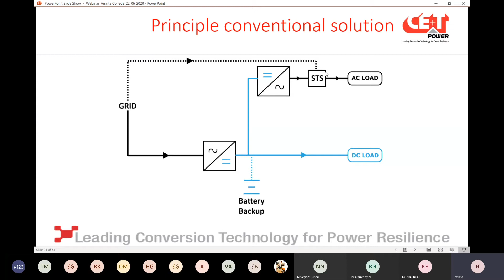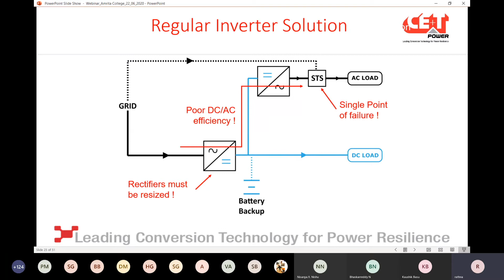There is a single point of failure with the static switch: when the static switch fails, you lose the load. The AC load is more critical here, and the AC loads are the value-added servers in the telecom data centers. Our solution uses TSI modules, feeding AC to AC conversion, and taking DC from the existing battery to convert DC to AC to supply the AC load, avoiding the single point of failure.